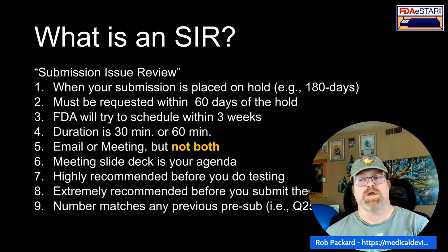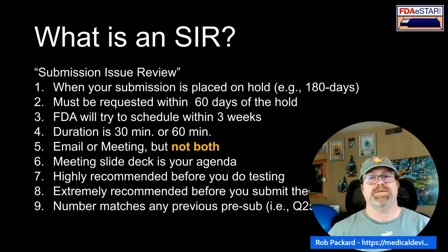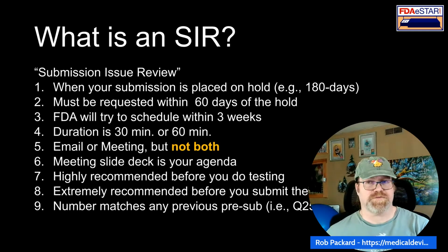We highly recommend that you do an SIR meeting before you do any more testing so you don't waste money. But it's extremely recommended that you do it before you submit a supplement to the AI hold, because you don't get 2 AI holds 99% of the time. It's less than 1% of the time you get 2 AI holds. So do not squander your opportunity to ask an SIR question. It's just a 3-week wait. It's worth it. So I highly and extremely recommend doing it before you submit your supplement, because you don't get 2 shots at this.